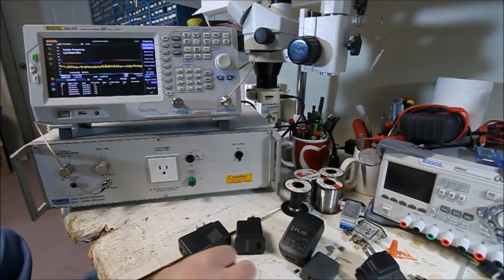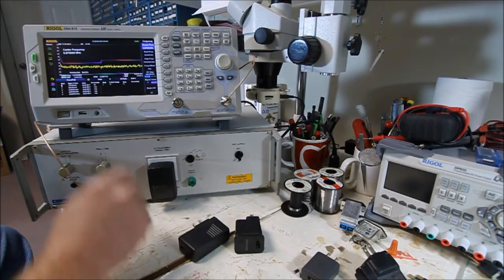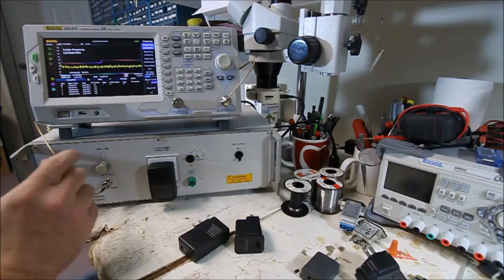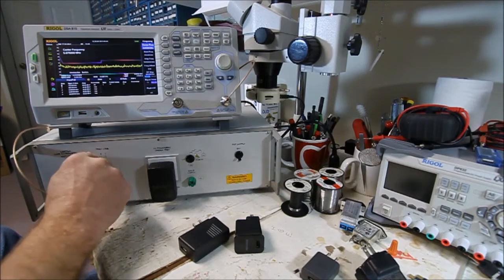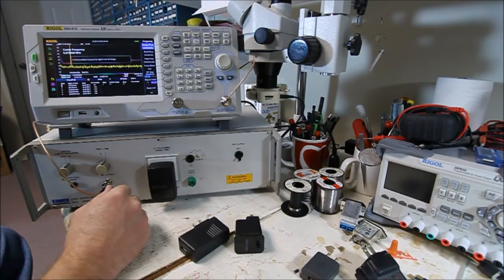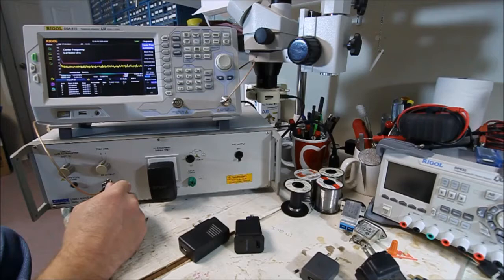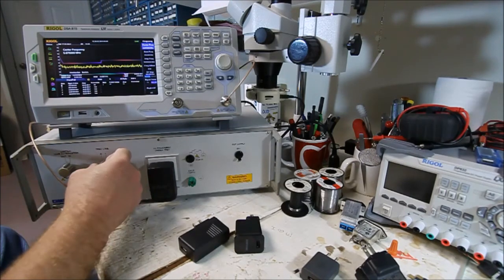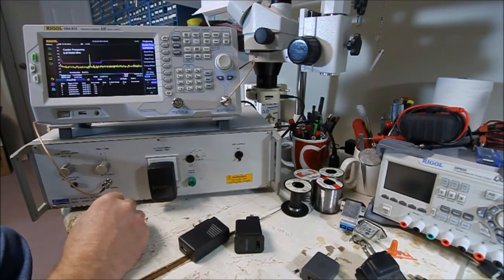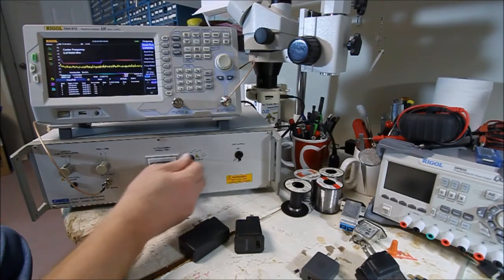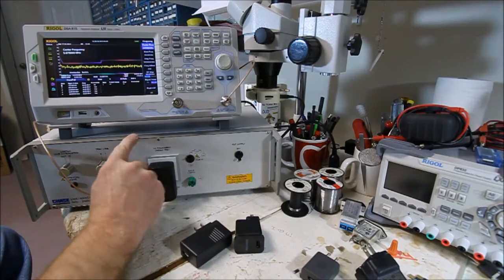Okay, for a little bit more detail, I'm going to take this nice adapter here, plug it back in. We'll see that it's clean. This LISN's kind of nice in that I can test both phases. I'm looking at the neutral line right now. I'll flip this over, a little bit of transient noise right there when I flip to the different phase. We can see that noise off the line, noise on the neutral, they're the same. I can also reconfigure how the earth ground is connected on this box. No effect.